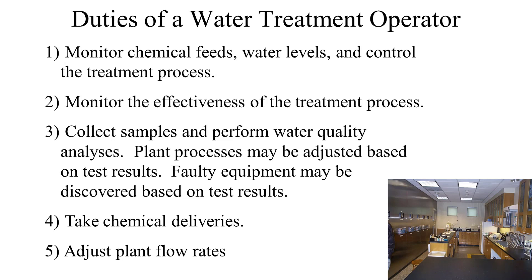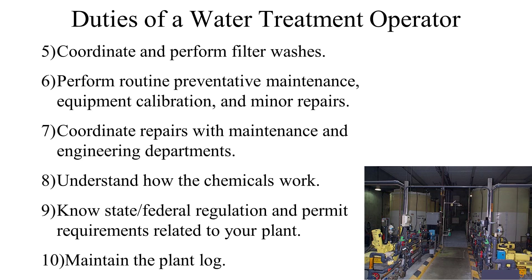As the demand for water in the distribution system changes throughout the day, the amount of treated water leaving the plant also changes. The operator is responsible for adjusting the plant flow rates. The filter removes particles from the water, and typically every two or three days a filter needs to be washed. Washing a filter involves taking it out of service and reversing the flow so the particles are removed. In some utilities, the operator is also responsible for maintenance activities such as instrument calibration and minor repairs.